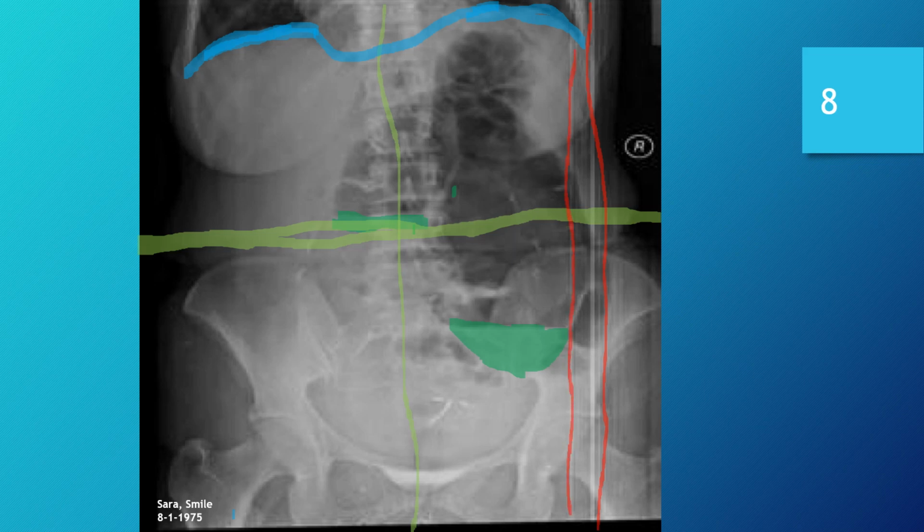We're just taking our stuff in order so that we make sure that we do our process the way we need to. Those almost look as though they are roller artifacts from a CR system. It's quite possible this is a CR image and that their equipment is having some issue.